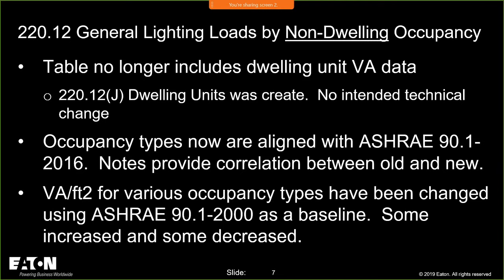I'm going to look at my 2020 and my 2017 code book. That way, I'm going to open both of those so I can do a little bit of a comparison for all of you guys and gals. So 220.12 used to say general lighting loads by occupancy, and in there was the line "in any of the preceding occupancies except one family dwellings and individual dwelling units of two family and multifamily dwellings," they had that one in there, and also up at the top they had dwelling units, which was 3 VA per square foot. So what we did was we removed the 220.12 references to dwelling units, and then we modified J.